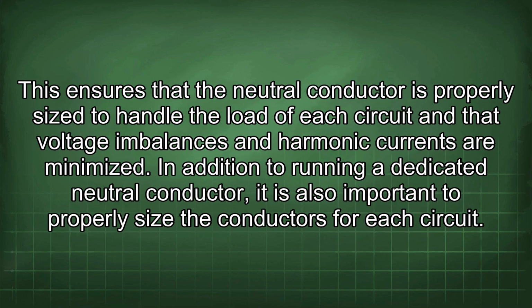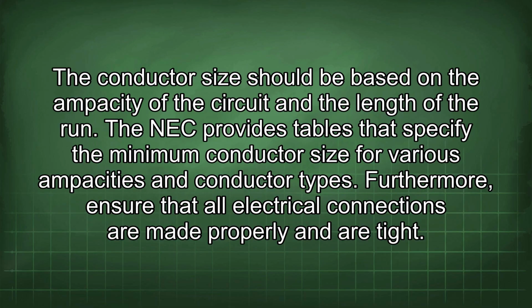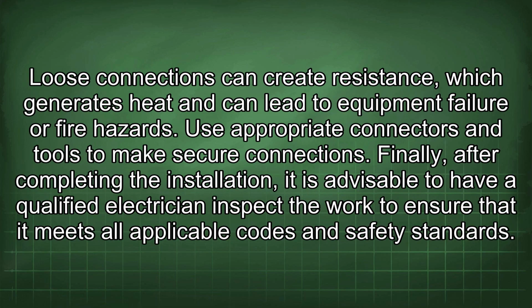This ensures that the neutral conductor is properly sized to handle the load of each circuit and that voltage imbalances and harmonic currents are minimized. In addition to running a dedicated neutral conductor, it is also important to properly size the conductors for each circuit. The conductor size should be based on the ampacity of the circuit and the length of the run. The NEC provides tables that specify the minimum conductor size for various ampacities and conductor types. Furthermore, ensure that all electrical connections are made properly and are tight. Loose connections can create resistance, which generates heat and can lead to equipment failure or fire hazards. Use appropriate connectors and tools to make secure connections.